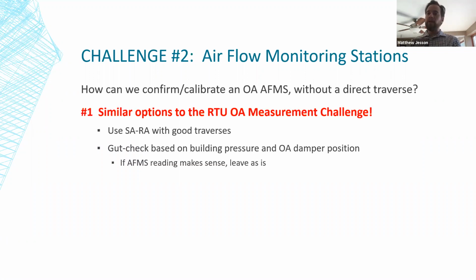The first is that you've got very similar options to what we just talked about with measuring rooftop unit outdoor air. If we can get a good supply minus return with good traverses, then I would hang my hat on that as compared to the airflow station reading.